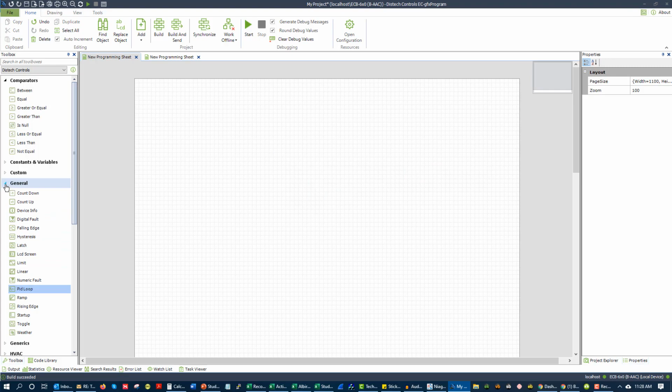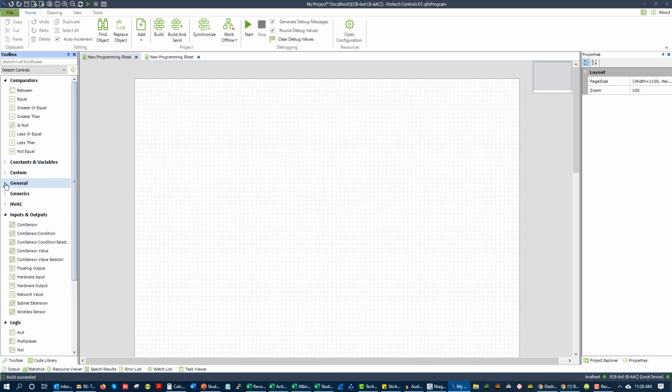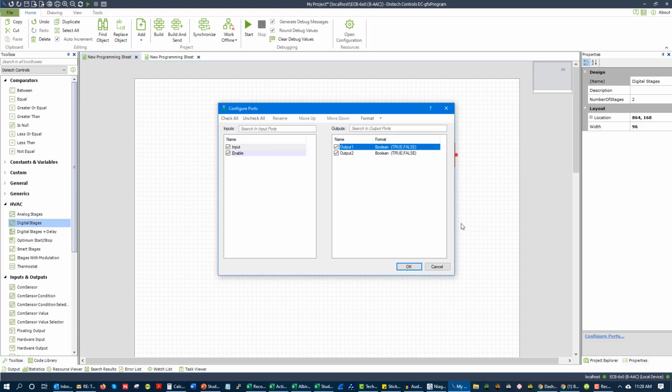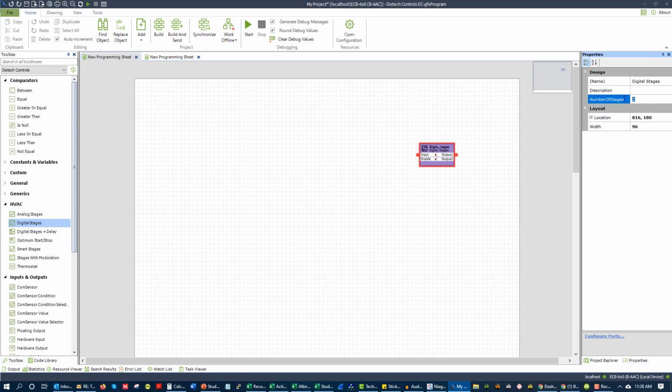The next control mode that we'll talk through, and this will probably be the last control mode for this video, is staged control. Staged control allows you to turn on multiple outputs. There are different ways of doing this. Some software, like GFX, enables you to have a block that allows you to set the number of stages. Based on the number of stages, it has a hysteresis built in, which says if it goes above this value, it will turn on, and it won't turn off until it drops below a different value. Then it stages on and stages off.